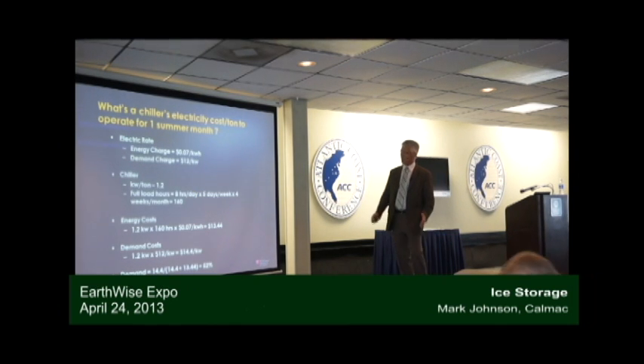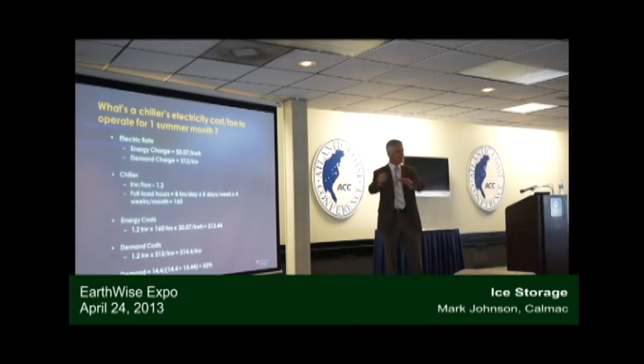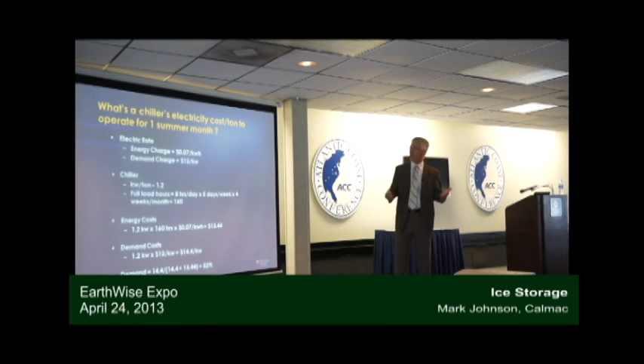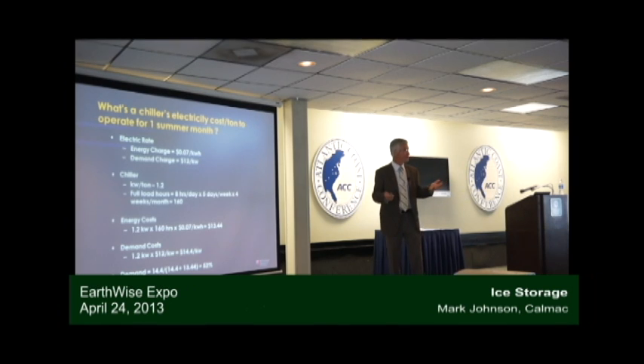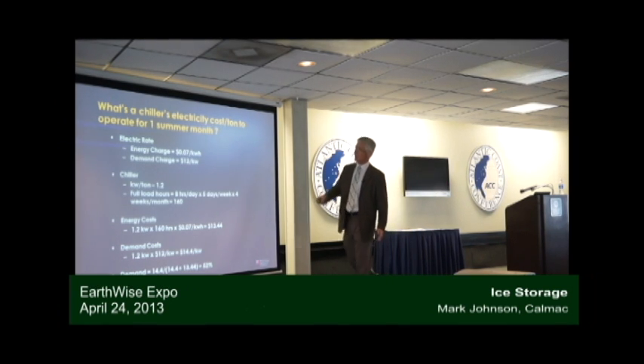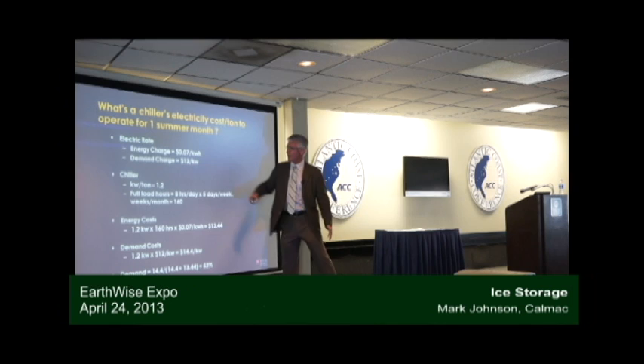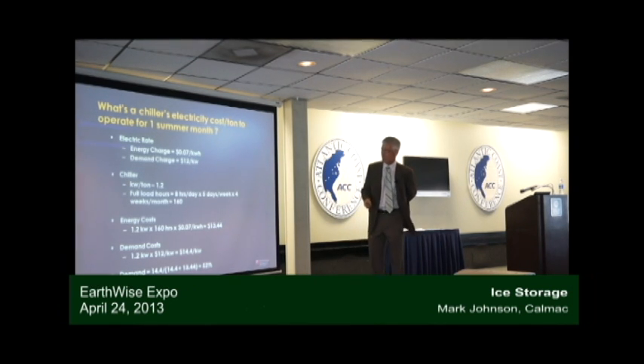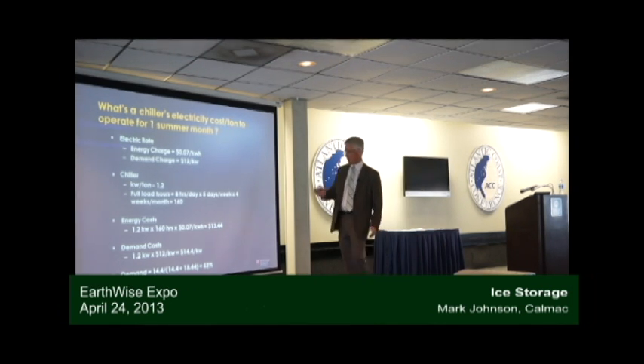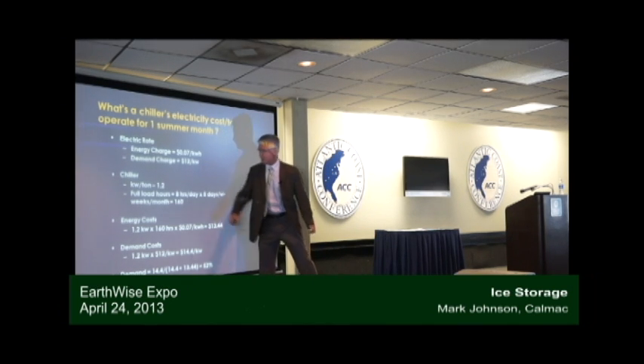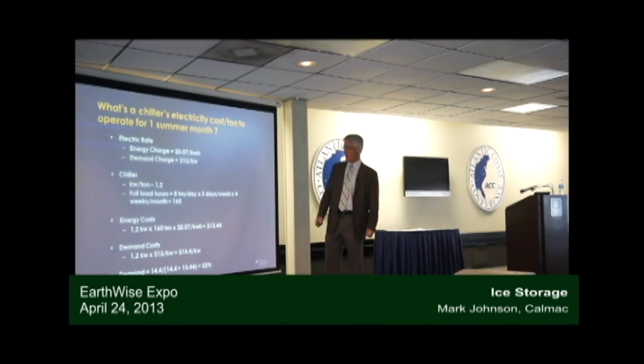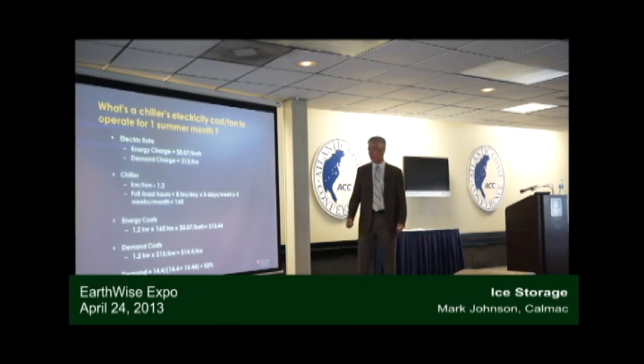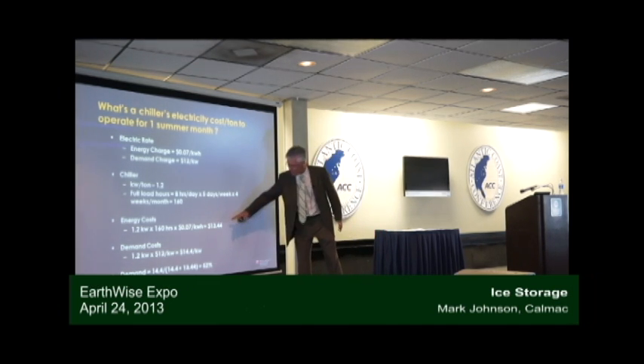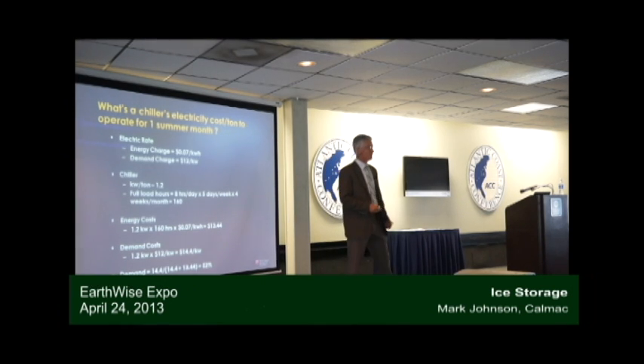I want to drive this home a little more, because I think this gets missed a lot as we design chiller plants for the future. What's it really cost per ton to operate for a summer month? Here's an electric rate at 7 cents a kilowatt hour, $12 a kW, a very typical rate. We're looking at an air-cooled chiller at 1.2 kW per ton. If we operate that chiller about 160 hours a month, our energy charge is going to be $13.44 that month.